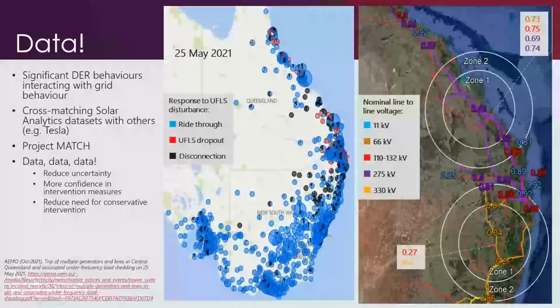The black ones are the percentage of inverters in that postcode that disconnected. You can see a very large concentration of them around here in northern New South Wales, and another concentration of them here in Queensland. Those areas are very closely correlated with where we saw very low voltages on the grid. You can see the epicenter here, with per unit measurements on the transmission network down at 0.2 per unit or 0.3 per unit, very low voltages, which we would fully expect to cause disconnection of inverters.